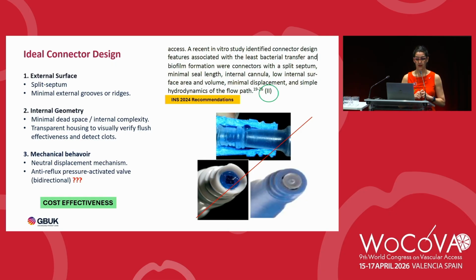This is very important because it allows us to visually verify that we are doing a good flush with our syringe, and to detect clots as well. And for the mechanical behavior, the neutral displacement mechanism, we have said it's fantastic, and also the anti-reflux, but I place some question marks at the end because sometimes this technology can be a little more expensive, and that is also something we have to deal with, costs. So the point is that we need to make a good choice between the cost and the effectiveness of the devices.